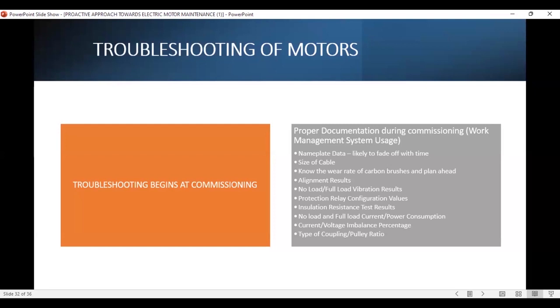Current and voltage imbalance. Voltage imbalance is very dangerous. Even 1% of voltage imbalance is not acceptable. 1% motor imbalance means you must stop, investigate, and resolve. Current imbalance can be tolerated up to about 10%, but voltage imbalance is a no-go area.